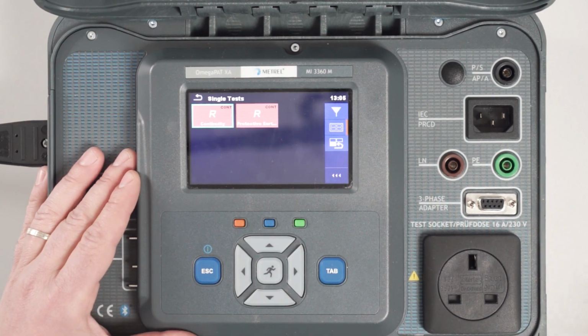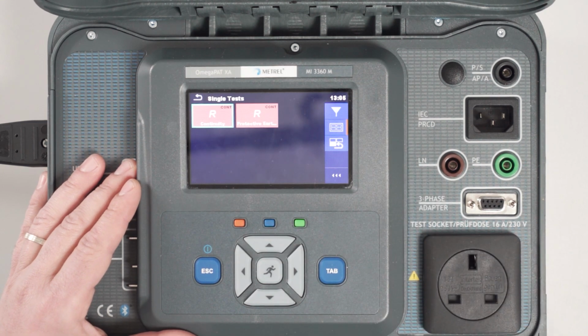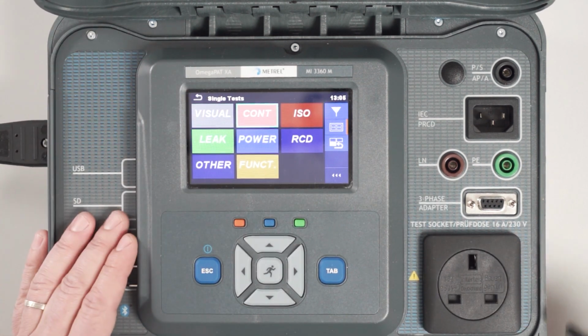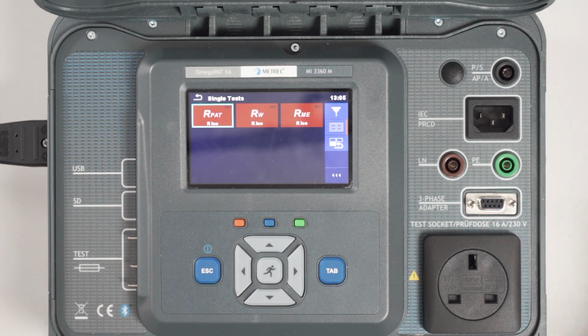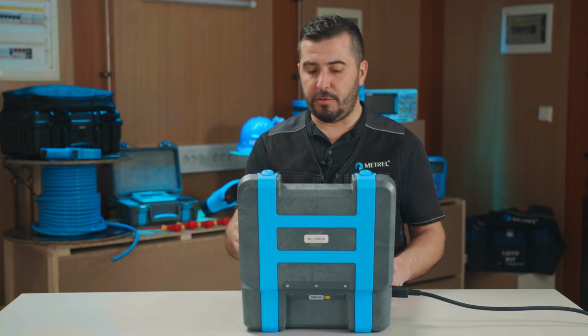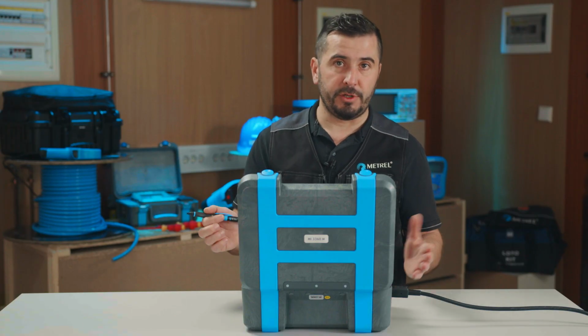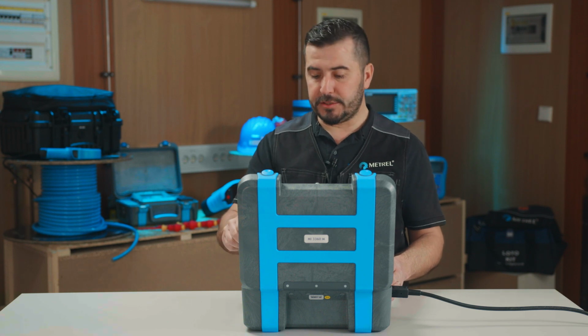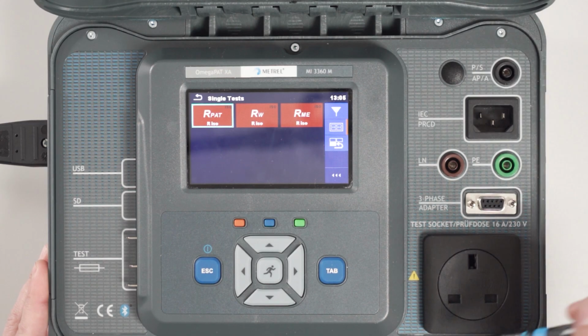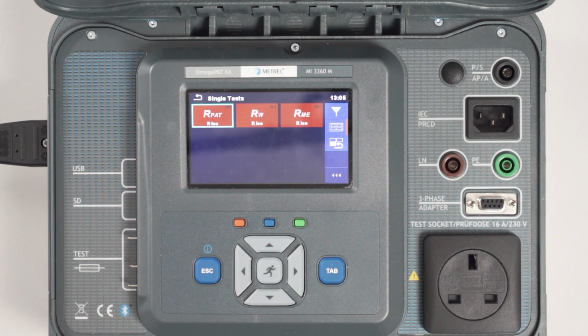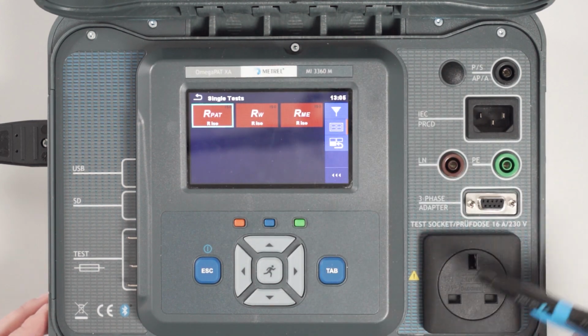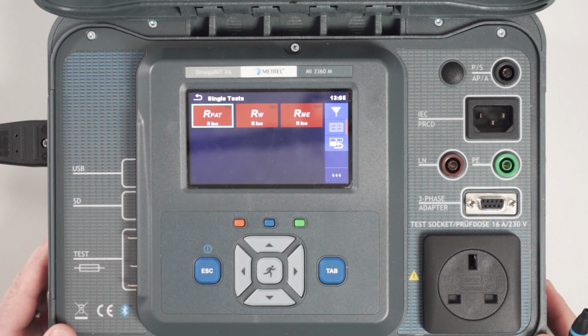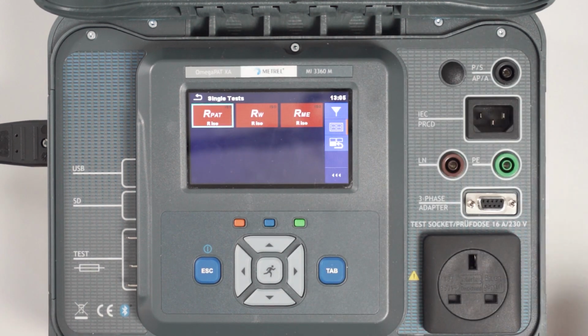Same measurement, but the caption is different because it is applicable for the medical appliance testing. Then we have the insulation resistance menu, from where we can select insulation for portable appliances, this one being executed here or with a probe. Then we have insulation resistance for welding and insulation resistance for medical. The main differences between these measurements are in the predefined or preset limits.